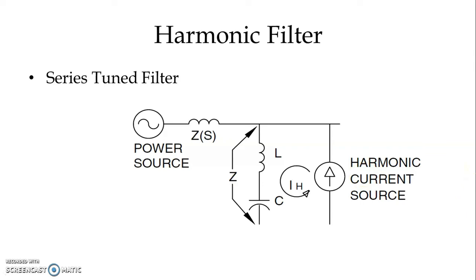The series tuned filter is designed in such a way that at a certain frequency the impedance of the filter is at its lowest, and the impedance of the power source is quite high compared to the impedance of the filter. That is why the harmonic current, instead of propagating to the power source and other connected equipment, will circulate between the current source and the series tuned filter.